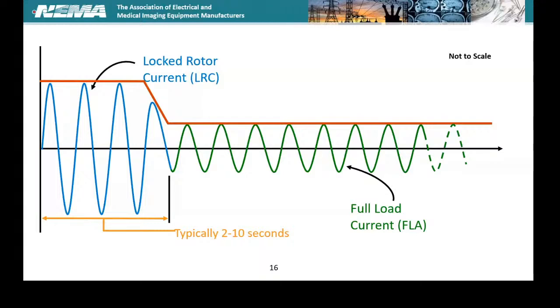Yeah, and in reality too, Jack, that first half cycle is not symmetrical. It's typically asymmetrical because of the inductance to resistance characteristics of the load and the system. So that first half cycle is a doozy, and normally we don't really plot that or talk about it much, but the code and the multipliers that the code has for that initial inrush current are typically enough. But you could come across areas where, even if you design it and you're cutting it kind of close from a lower amp rating, you could still trip that circuit breaker or open that fuse.